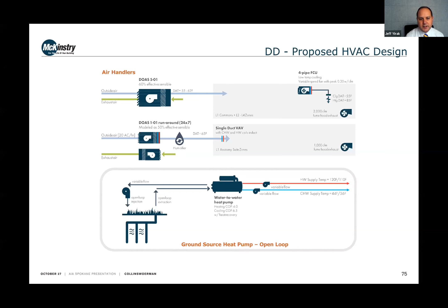In order to track the energy impact of the design, we created two energy models. One was at the end of the SD stage, which Jeff mentioned was essentially a code minimum building with an EUI of 83. Throughout the TCO process, the design was significantly improved, and we wanted to show the EUI change of eliminating natural gas for heating, introduction of an efficient ground source heat pump system with DOAS, and improved envelope assembly, improved daylighting, and added external shading devices. With these changes included, a final energy model was created at the end of the design development phase, which resulted in an EUI of 46.